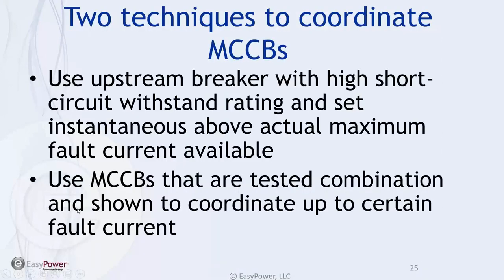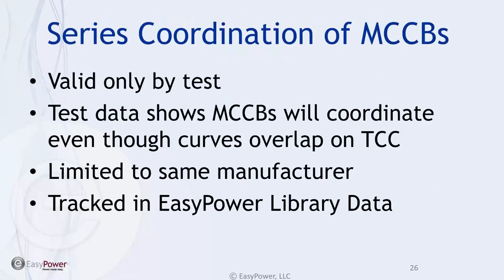Based on fault current, there is potential for coordination up to a certain point. Looking at TCC curves for two devices, a fault to the left of the overlap guarantees coordination because the downstream breaker will trip first. The problem exists when we're in an area of uncertainty in the overlap region. MCCB manufacturers are testing for series coordination, where guaranteed coordination based on testing can validate certain combinations.